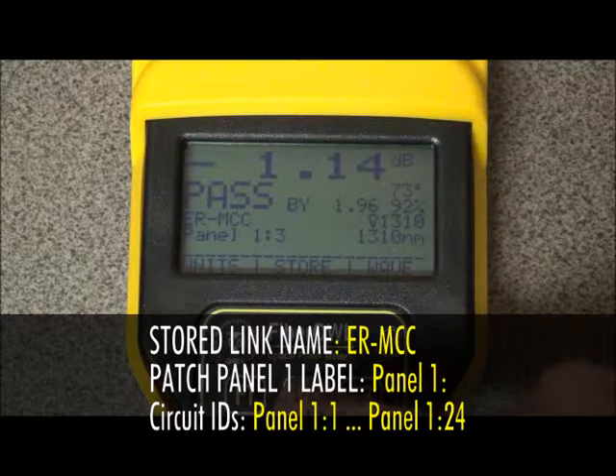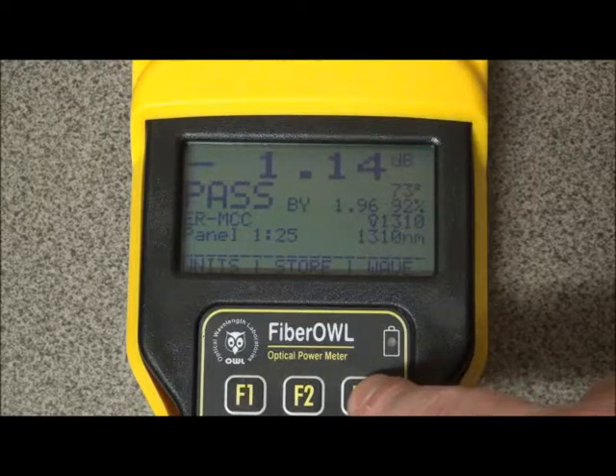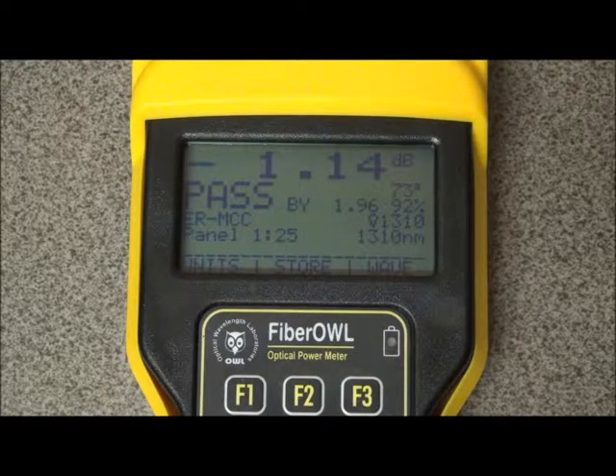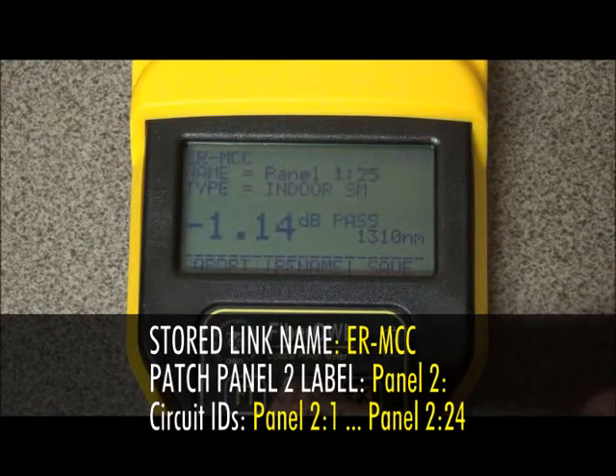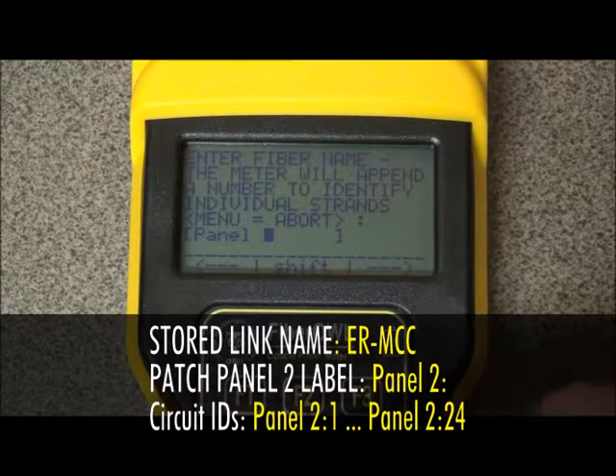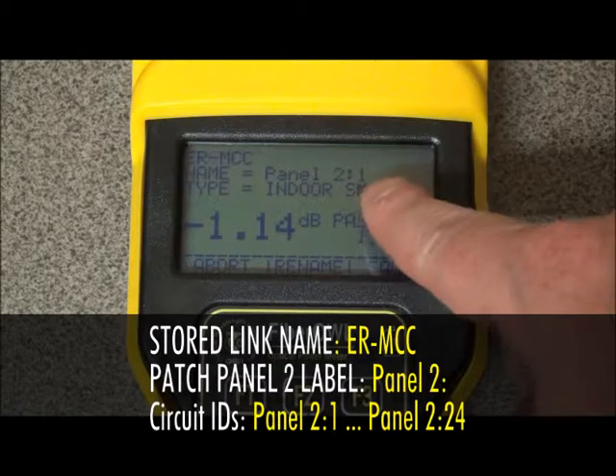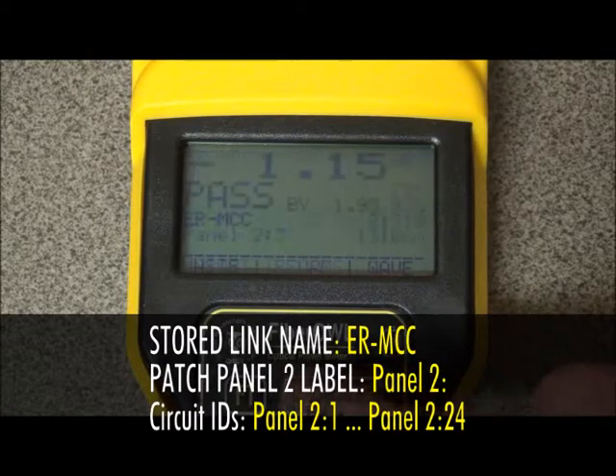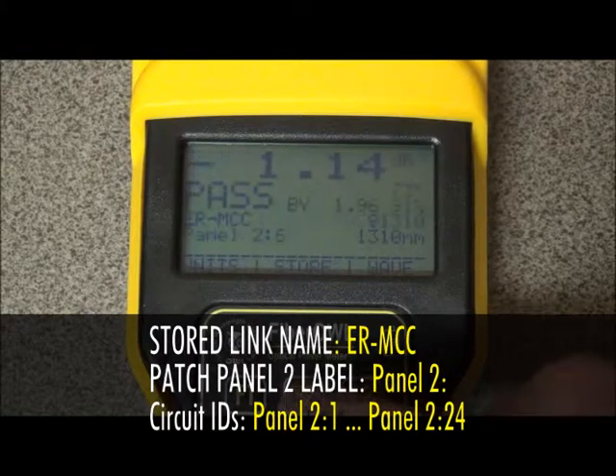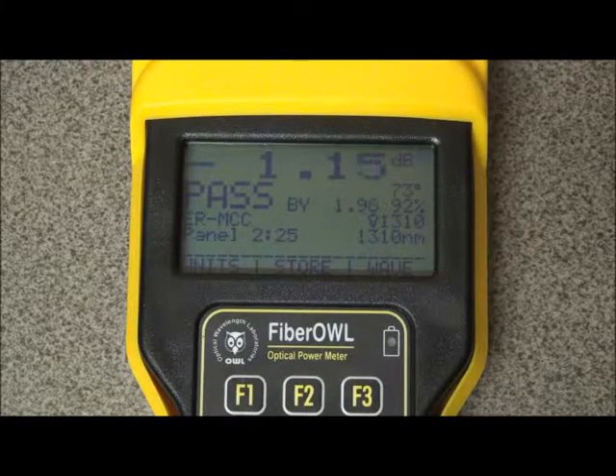Speeding through the process — we have now stored up to 24 readings and are prompted to hook into port number 25. We don't have a port 25, but we do have the first port on patch panel number 2. When storing this reading, hit store, then rename: backspace and put 2 colon, then hit done. As you can see, we start back at port number 1. Save and continue storing data until we reach fiber port number 24. Store reading number 24.